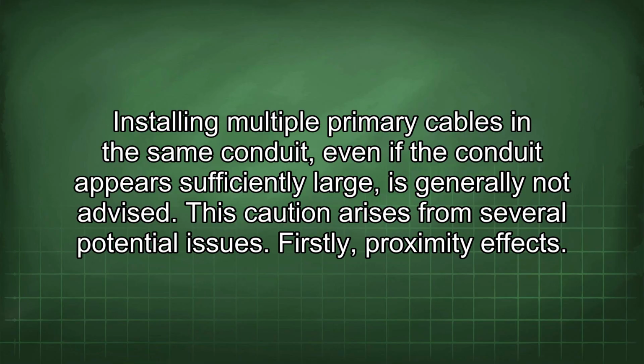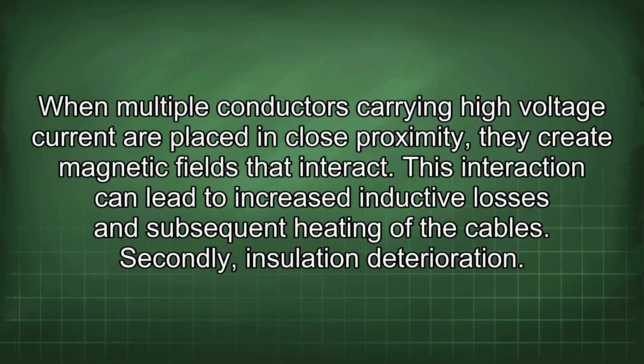Installing multiple primary cables in the same conduit, even if the conduit appears sufficiently large, is generally not advised. This caution arises from several potential issues. Firstly, proximity effects. When multiple conductors carrying high voltage current are placed in close proximity, they create magnetic fields that interact. This interaction can lead to increased inductive losses and subsequent heating of the cables.